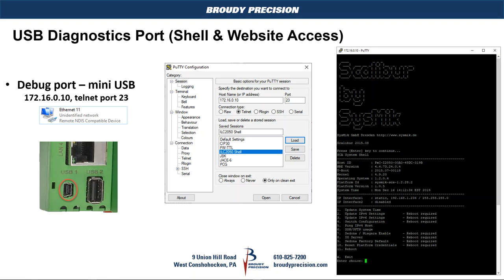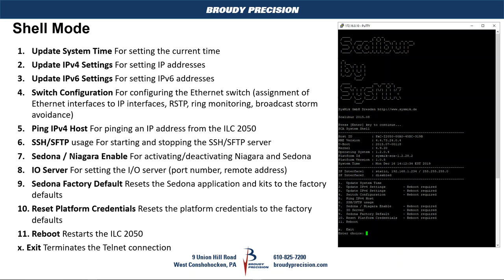When you plug in the ILC it automatically becomes 172.16.0.10 and its telnet port is 23. The connection is set up on your computer and the IP addressing will already be set up for you. In PuTTY, set it up as a telnet session with host name or IP address 172.16.0.10 and port 23, and once you go in you will come up with a screen that gives you various information: host ID, software versions, IP addressing, and then the menu options.